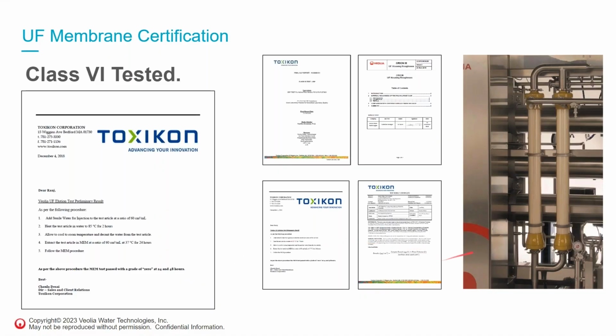The other thing we found was these polysulfone UF membranes came from a supplier. They supplied us with a lot of documentation, but there wasn't quite enough documentation there. So we've actively ourselves sent these away to be tested at a laboratory in the US, where they've cut them up and destructively tested them. So we have Class 6 approval certification on those particular units, and they did all the elution tests as well at above 85 degrees to prove that there was no risk in terms of producing parenteral drugs for any leachables from those plastics.